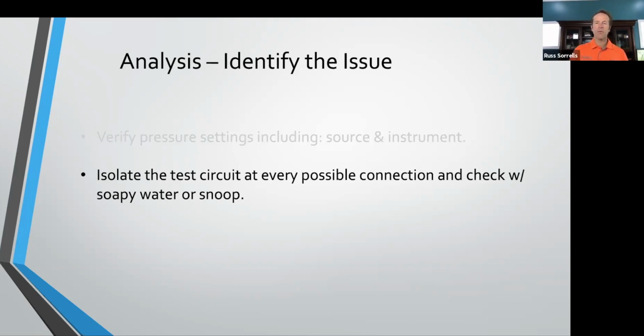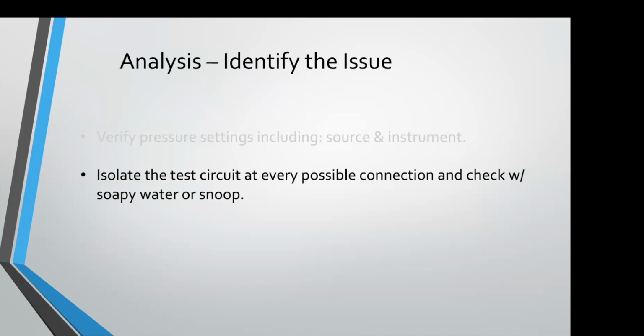I've seen these problems before in these hoses, especially with the Nylaflow, because it's so rigid that they'll have a small crack in it, but because of how it might be resting, it doesn't show up as a leak until you bump it or touch it, and then it begins to leak. Those are real challenges to find, but we've definitely seen that. Anything to add? And then fittings, if you have force on compression fittings that are at an angle, that's another place to double check for leaks.